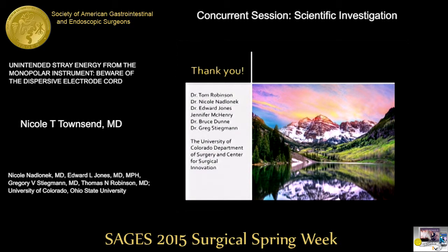And so what you can do is actually remove the power generator from that tower, place it on the other side of the patient, and that completely removes the monopolar generator from all of the other instruments. That is a very simple maneuver to isolate that power generator and decrease the risk of stray energy transfer in your operating room.